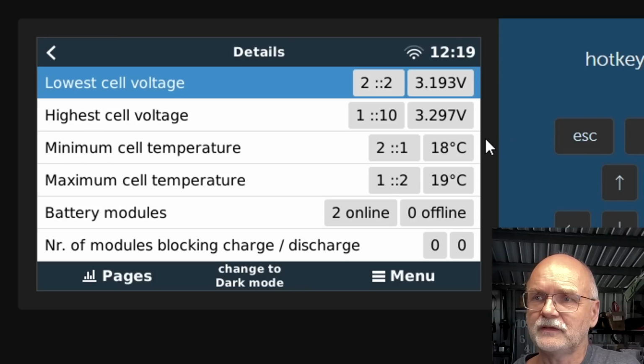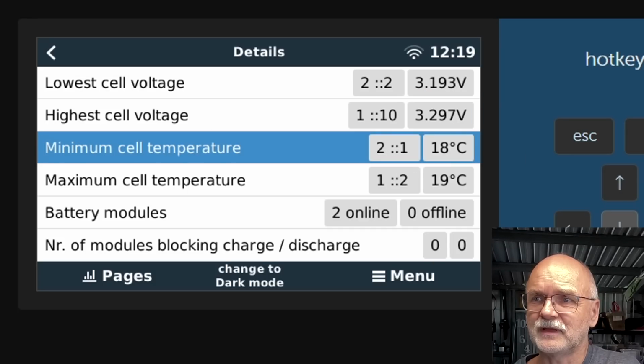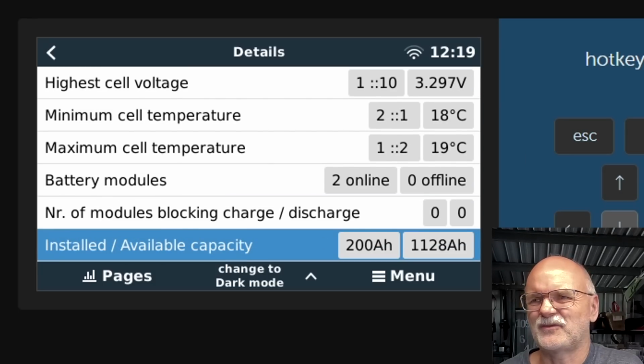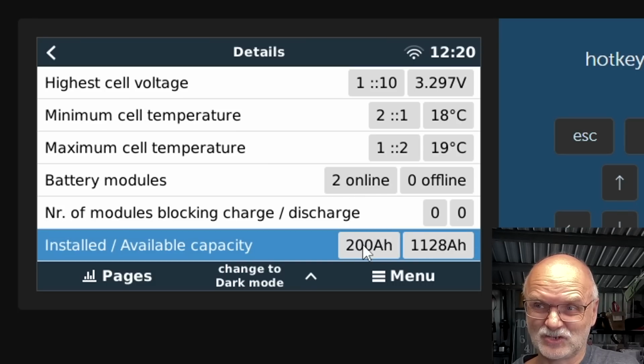Let's see what we have. Yes, there is communication. See, battery number 2, this is the new one, has the lowest cell voltage, and it also has the minimum cell temperature of 18 degrees. These numbers make sense, so obviously there is some communication going on. Yeah, and this one is still completely off. It sees 2 batteries online and just doubles the capacity from the first battery.